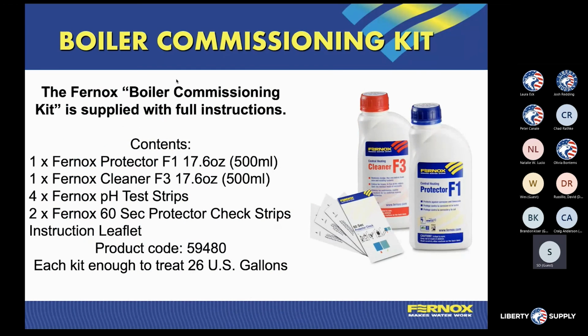We do sell our systems in what we call a commissioning kit. If you don't buy the test kit as a standalone, it's going to give you one bottle in either the Express, which is the injectable style, or that pressurized can that we were talking about, or the liquid. It's also going to give you some pH test strips and some F1 test strips, so you can test where that system is. These are more of a litmus test, or just a dip style test, and we'll give you a little card to match up with those systems.